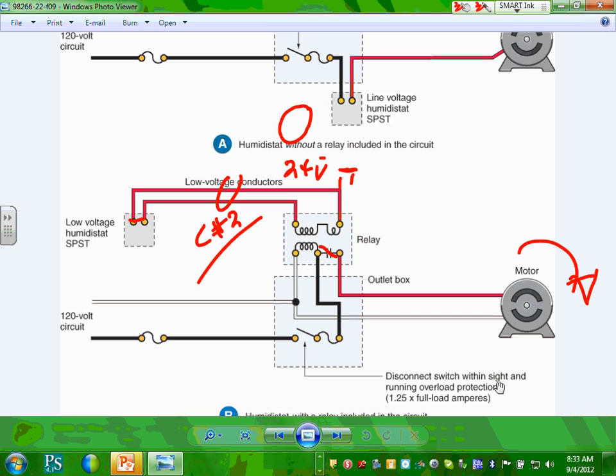The opposite is true when the heat goes lower than a certain value: it opens and de-energizes this 24 volt coil. The coil is right in here. It energizes the 24 volt coil, and when it de-energizes, it opens this contact. Now this contact is open and your motor is not working. And you still have to have a disconnect here. Remember that disconnect that comes with it. All these are built in, guys, built in.